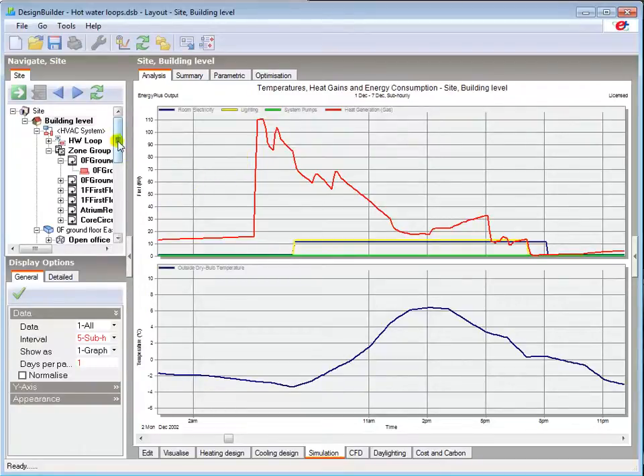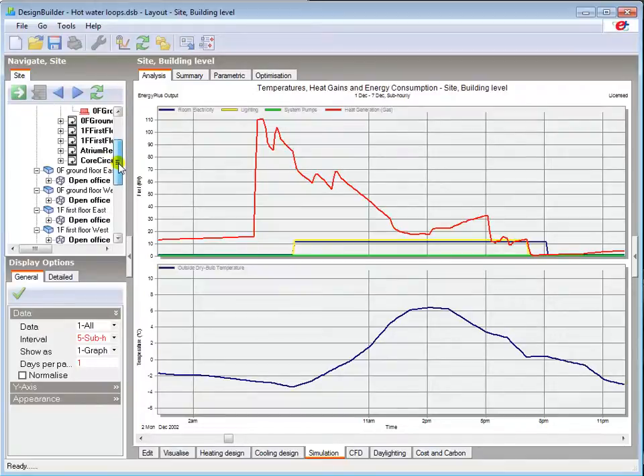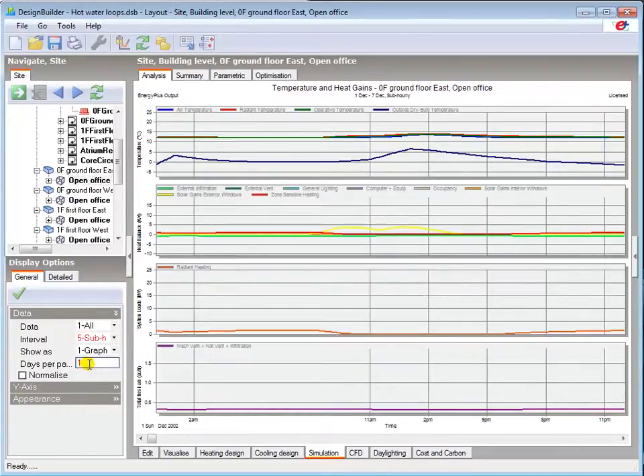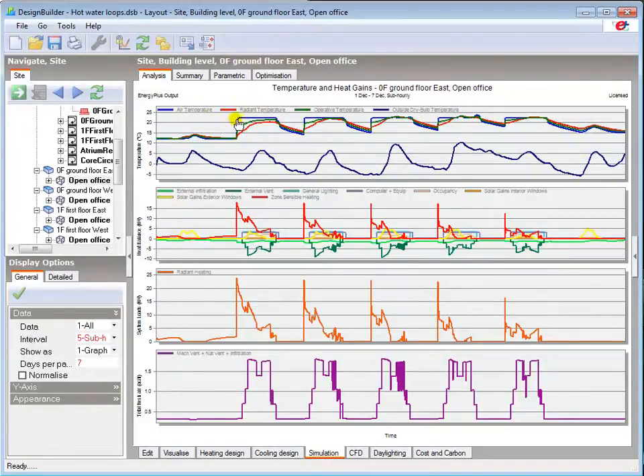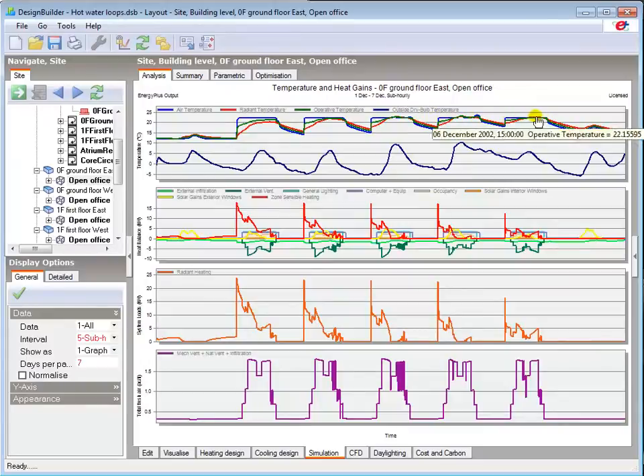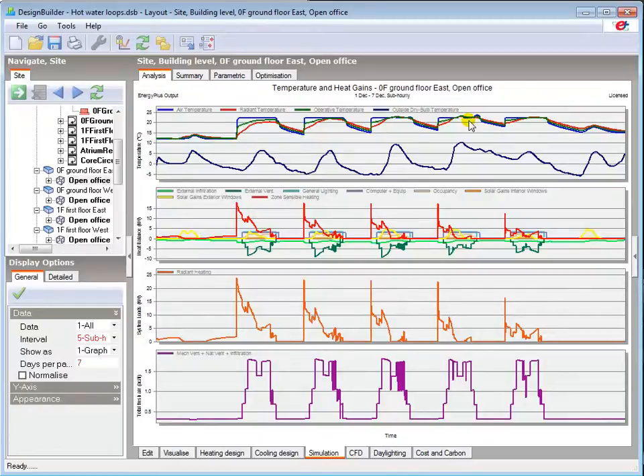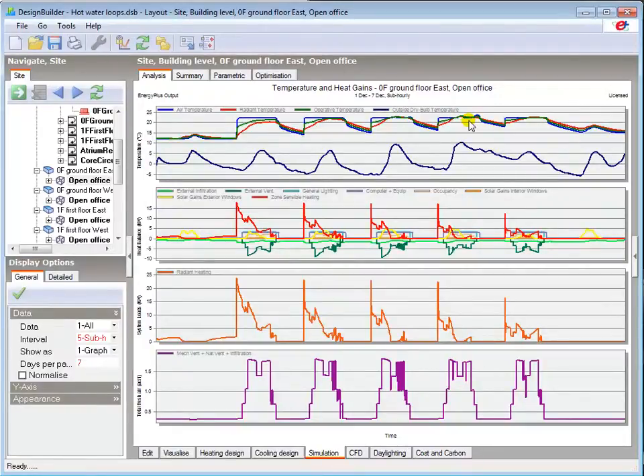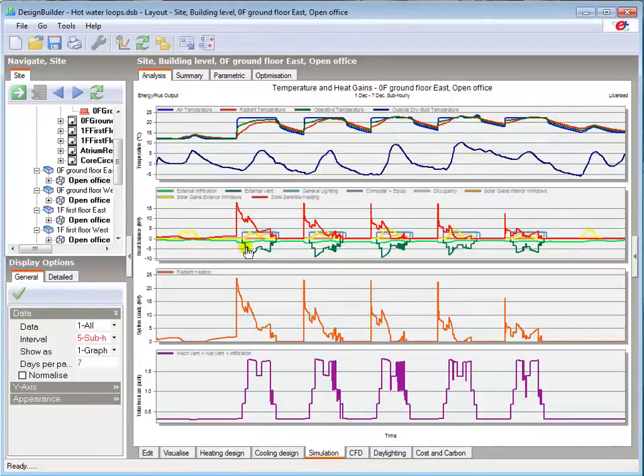Navigating now to the ground floor east office in the model, not in the zone group, and going back to a 7-day view, we can see that the heating setpoint is achieved during occupancy, showing that the system has sufficient capacity. With natural ventilation enabled and low outdoor air temperatures, the zone temperatures stay much lower than you saw in the previous Introduction to HVAC Loops tutorial. The only significant setback operation in this zone is at the weekend and on Monday morning, which would be expected at design conditions.